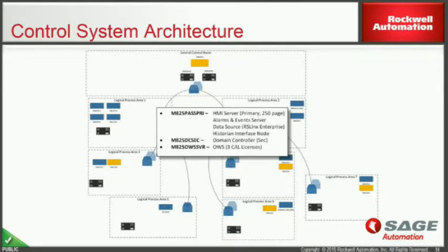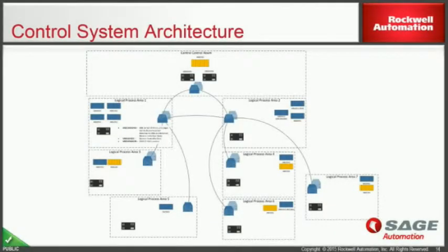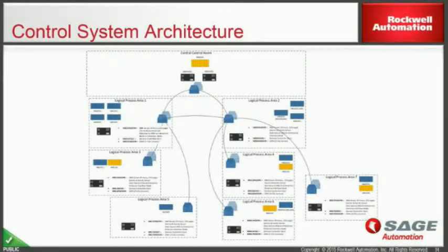Then we had 7 area-based server hosts, virtual hosts, and two server hosts up in the control room. The 7 process areas were identical in structure, where we had a primary HMI server running, a secondary domain controller, and operator workstation in each of the 7 process areas. The reason why we had distributed servers is because if there was, for whatever reason, a connection severed between the control room and the process areas, they could still actually function, could run in isolation for them to be able to shut down safely.